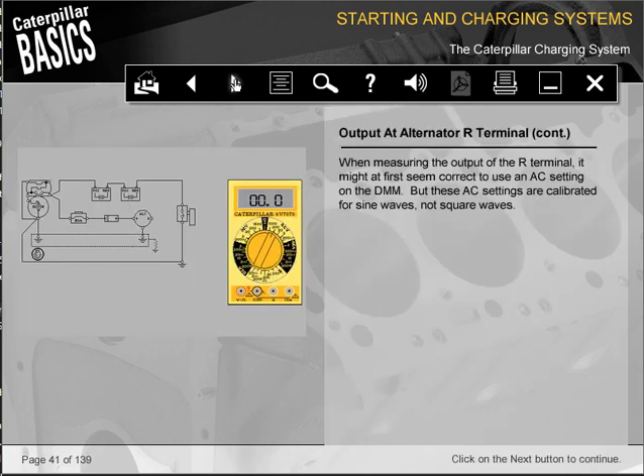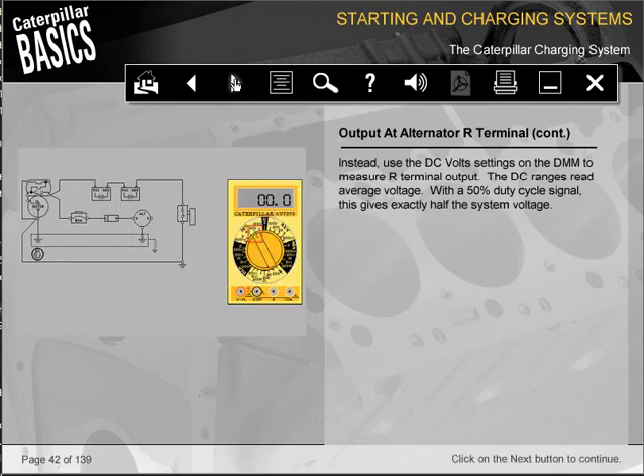When measuring the output of the R terminal, it might at first seem correct to use an AC setting on the DMM. But these AC settings are calibrated for sine waves, not square waves. Instead, use the DC volts setting on the DMM to measure R terminal output. The DC ranges read average voltage. With a 50% duty cycle signal, this gives exactly half the system voltage.